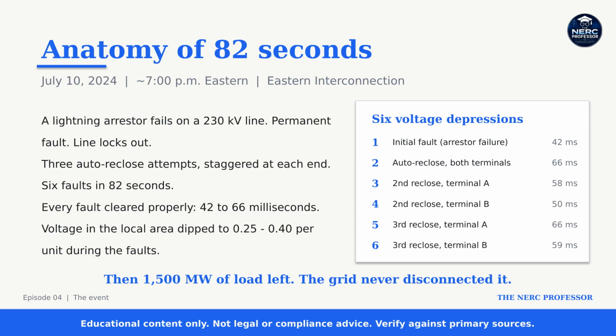Let's slow the event down, because the details are the whole story. A lightning arrestor fails. The line faults, and the fault is permanent. Protection clears it. Then automatic reclosing does what automatic reclosing does. This line was set for 3 reclose attempts, staggered at each end. Each shot closes back into the fault, 6 voltage depressions in 82 seconds. Every single one cleared properly. The dips lasted between 42 and 66 milliseconds.